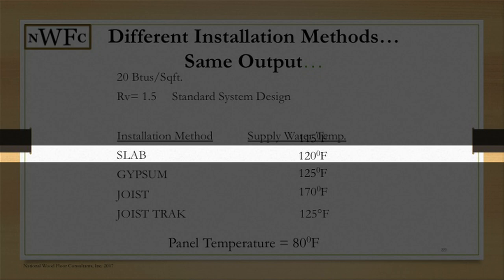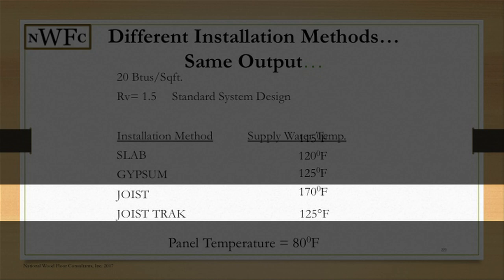When we look at slab construction, the water temperature is typically around 120 degrees. In a gypsum system it'll be around 125 degrees. Now look at how much that jumps in a joist system — that jumps up to 170 degrees. That's your supply temperature.